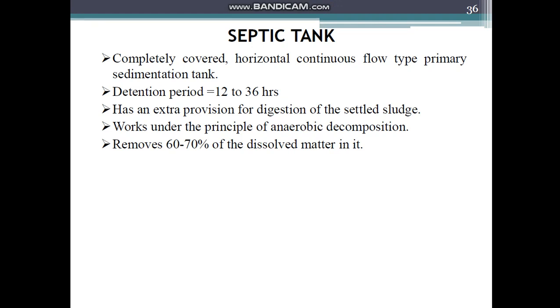A septic tank is a horizontal continuous flow type of sedimentation tank, directly admitting raw sewage and removing about 60 to 70% of dissolved matter from it. The effluent from such a tank will be sufficiently fouled in nature and will have to be disposed of either by subsurface irrigation, in soak pits, or treated in a treatment filter.